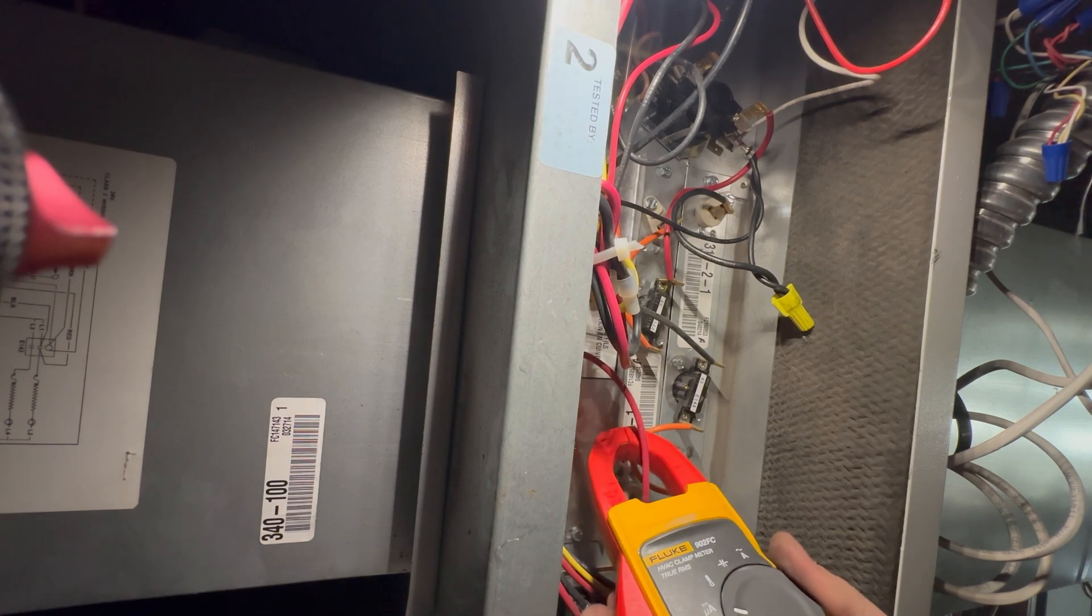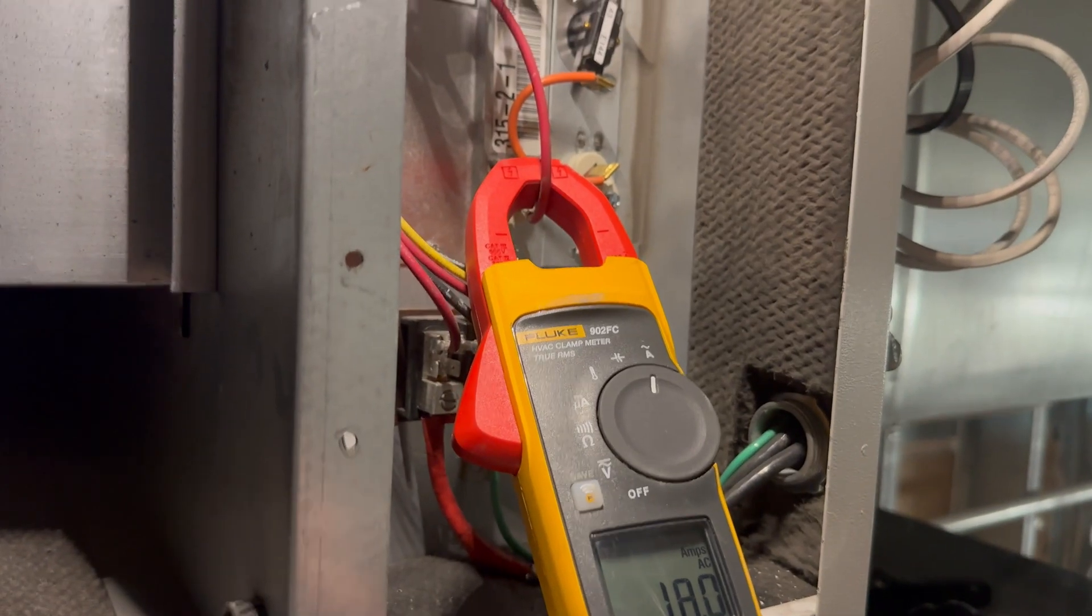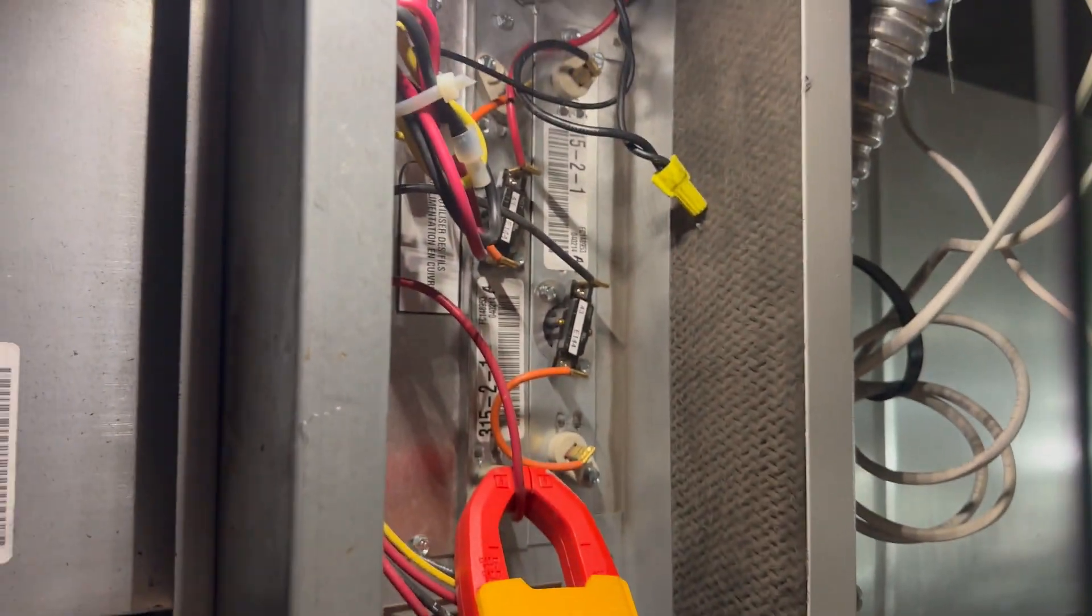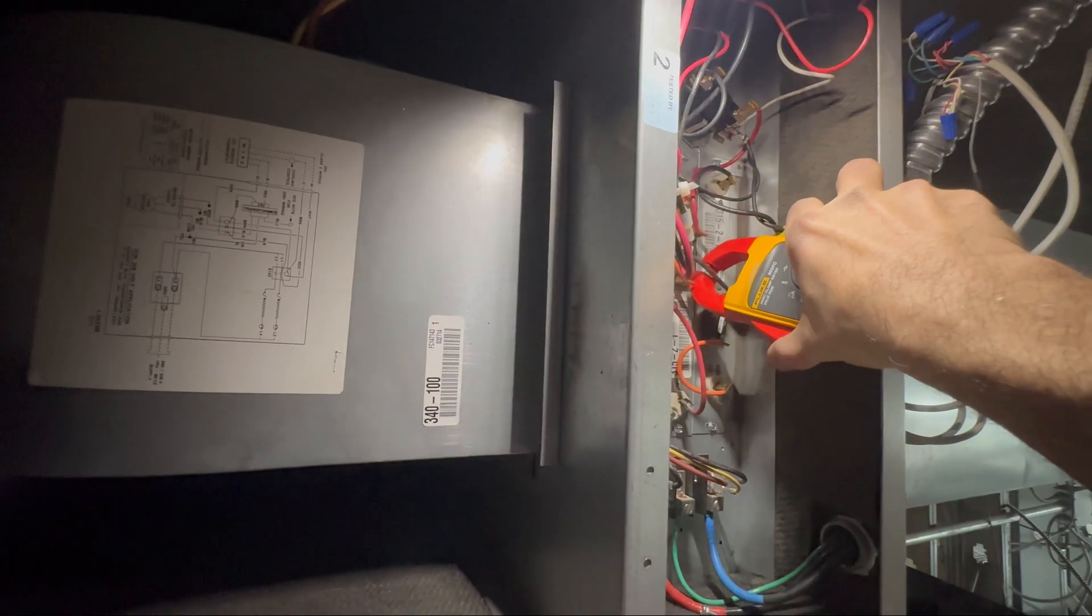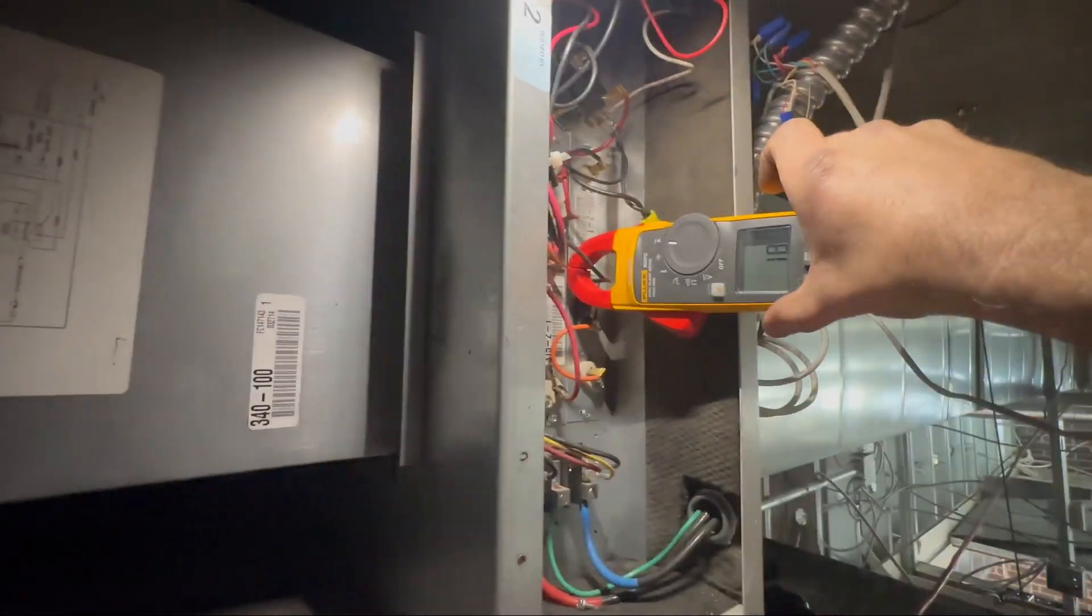Putting my amp clamp on one of the heating stages. Reapply power. And as you can see right here, we're pulling 18 amps on heater circuit one. And also got 18 amps on heater circuit two. So both heating circuits are working.